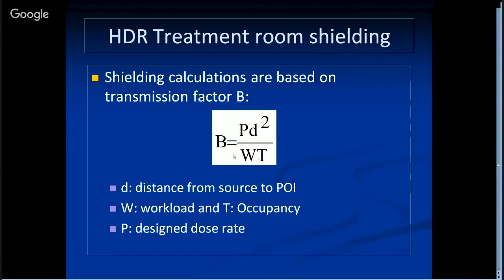You have the transmission factor B, and on the right side you have P, that's the ideal dose rate you're going to give to the public or controlled, uncontrolled area. D is the distance from your source to the point of interest. Then W is workload, and T is occupancy factor.